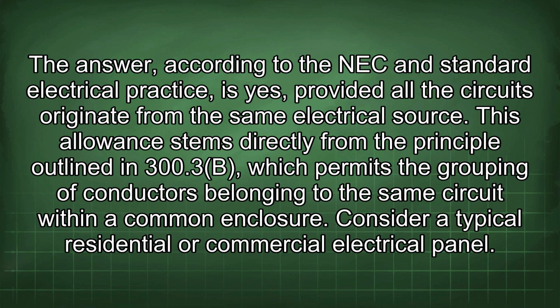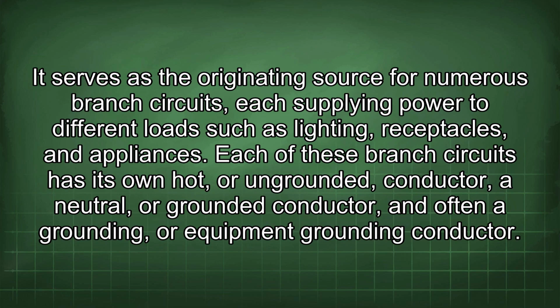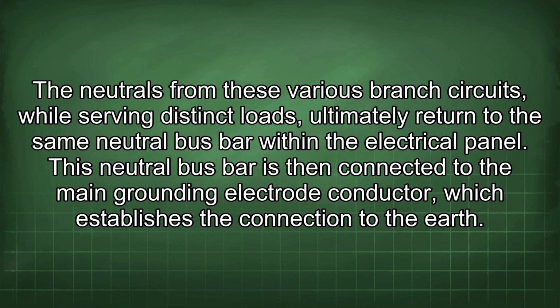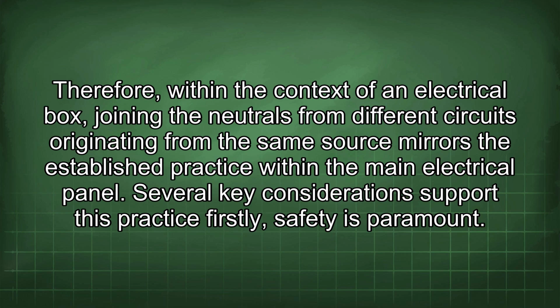Consider a typical residential or commercial electrical panel. It serves as the originating source for numerous branch circuits, each supplying power to different loads such as lighting, receptacles, and appliances. Each of these branch circuits has its own hot or ungrounded conductor, a neutral or grounded conductor, and often a grounding or equipment grounding conductor. The neutrals from these various branch circuits, while serving distinct loads, ultimately return to the same neutral busbar within the electrical panel. This neutral busbar is then connected to the main grounding electrode conductor, which establishes the connection to the earth. Therefore, within the context of an electrical box, joining the neutrals from different circuits originating from the same source mirrors the established practice within the main electrical panel.